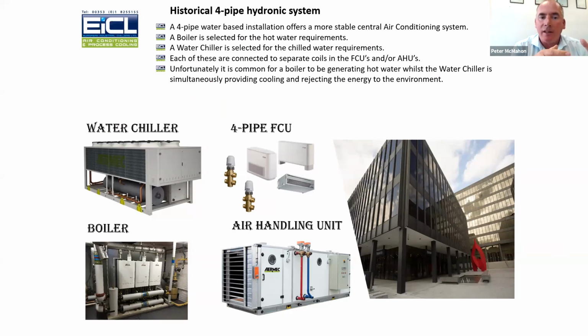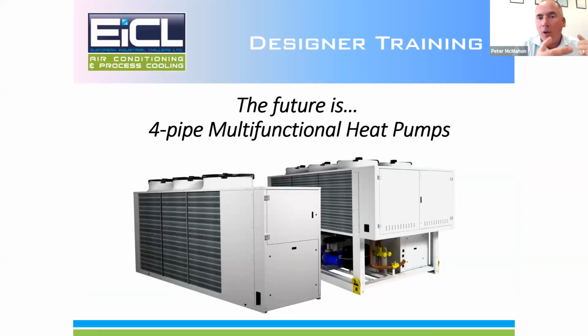So historically, we would have had the chiller that did the cooling. And if you know anything about refrigeration, as we're cooling the water, the refrigerant is absorbing that heat and we're dumping it through the condenser. At the very same time, you might have a boiler. I know a lot of you might have solid chip or solid fuel to generate heat when, like I said, we are dumping energy at the same time. So really you can see where we're going with this. We want to recover that energy. When I started giving this presentation quite a few years ago, we used to say the future is multifunctional heat pumps. It is now very much the norm. There are very few applications now that don't consider multifunctional heat pumps.